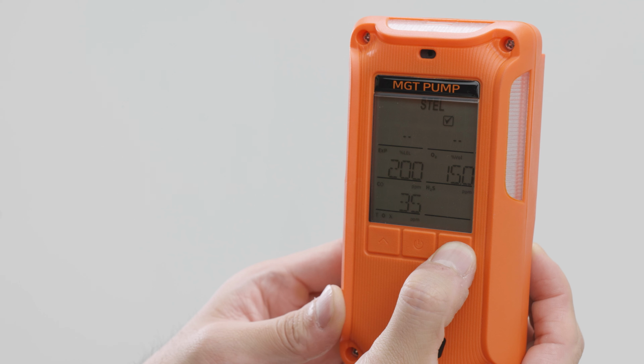Press the down button again to view the alarm set values for low, high, STEL, and TWA. Press the down button once more to view device information, including the firmware version, battery voltage, and current temperature. The next screen displays the date and time set in the device.